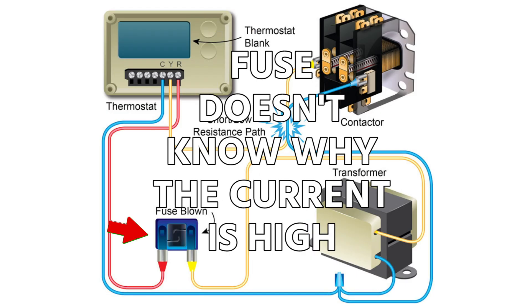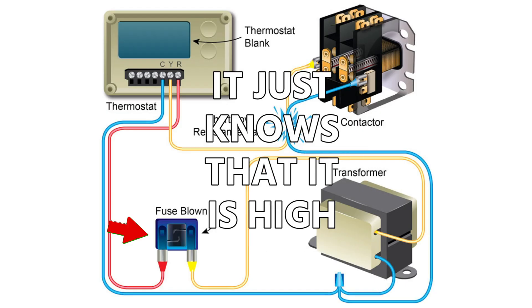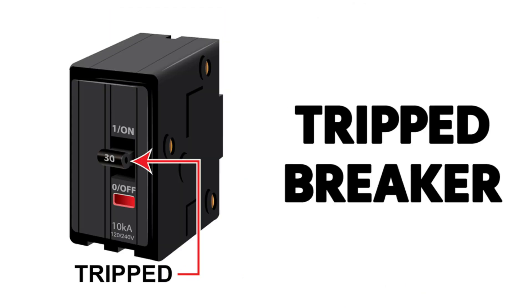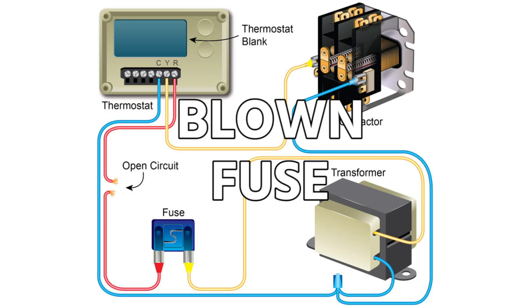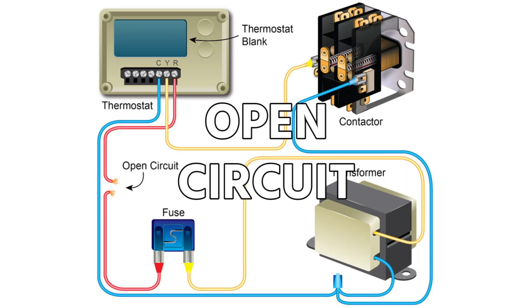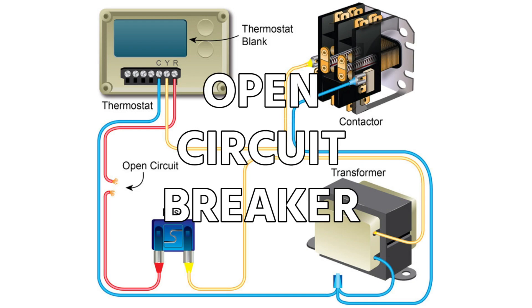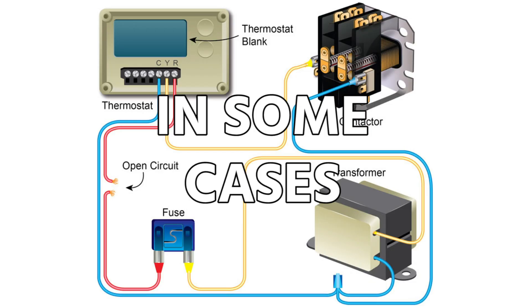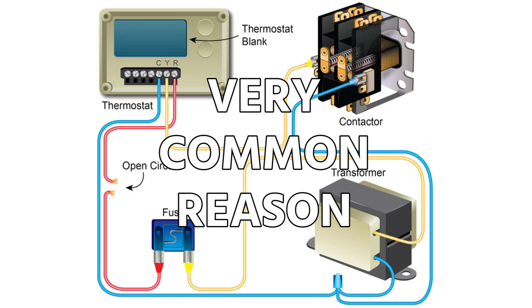A breaker or fuse doesn't know why the current's high — it just knows it is high, and that's why it trips or blows. So when you see a tripped breaker or blown fuse, that is an open circuit because the breaker has tripped or the fuse has blown. But that open circuit happened because of a short circuit in some cases — not all. That's not the only reason a fuse blows or a breaker trips, but it is one very common reason.